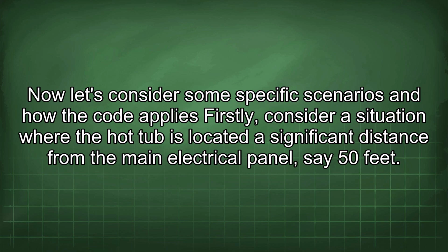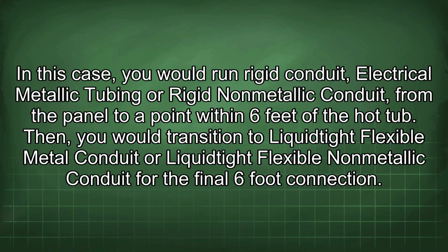Firstly, consider a situation where the hot tub is located a significant distance from the main electrical panel, say 50 feet. In this case, you would run rigid conduit, electrical metallic tubing or rigid non-metallic conduit from the panel to a point within 6 feet of the hot tub. Then, you would transition to liquid-tight flexible metal conduit or liquid-tight flexible non-metallic conduit for the final 6-foot connection.